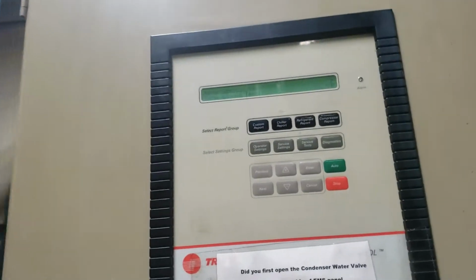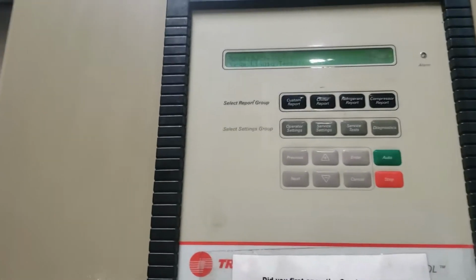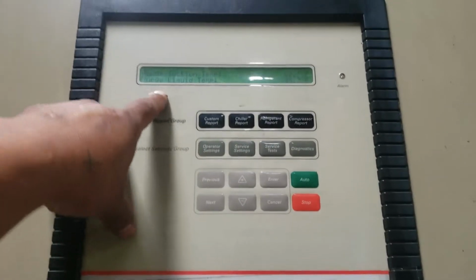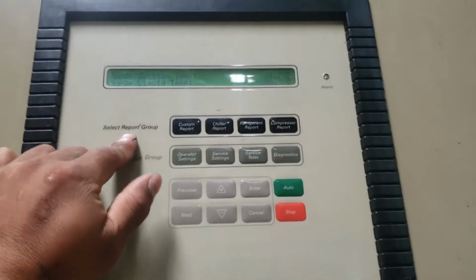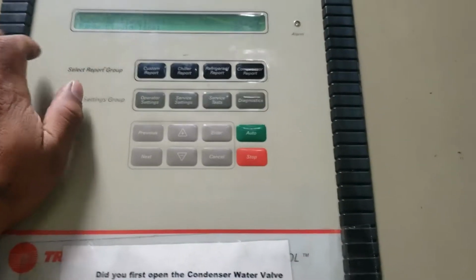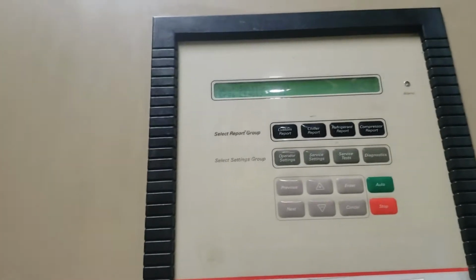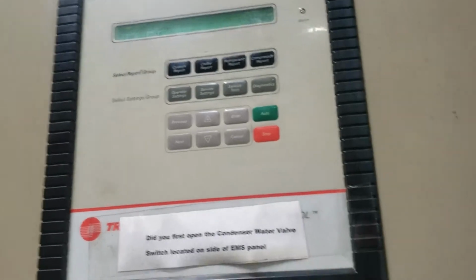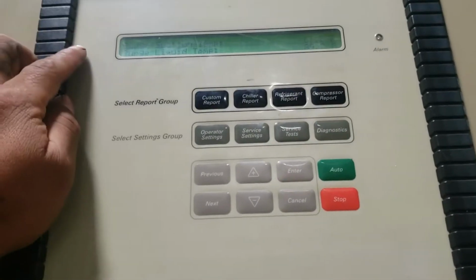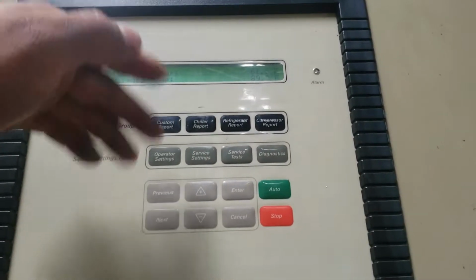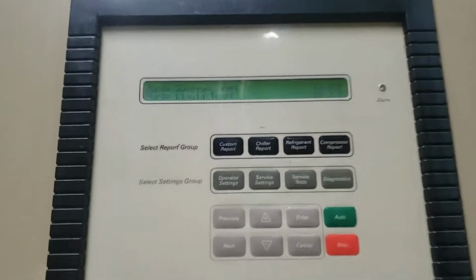But let's say I get air inside my chiller, that air is going to start filling up that evaporator on that Purge tank. So the heat transfer will not be that great, and so my suction temp will eventually start climbing down. Once it gets past 18 degrees, the pump kicks on and starts pumping out that air. And once that air is completely out, my suction temp will start to climb back up. But once it goes above 22, that pump is disabled.